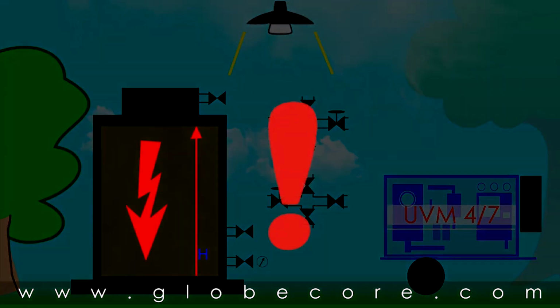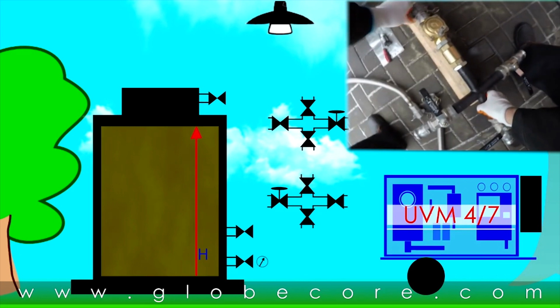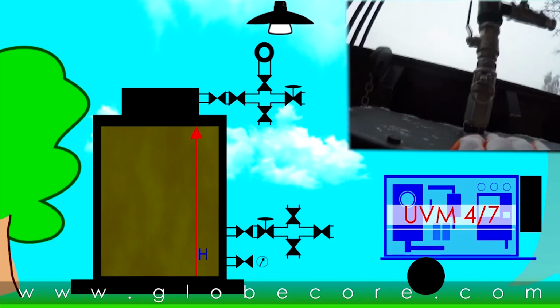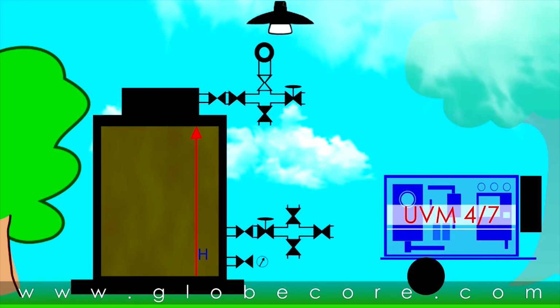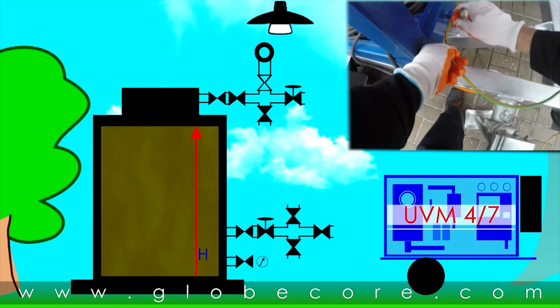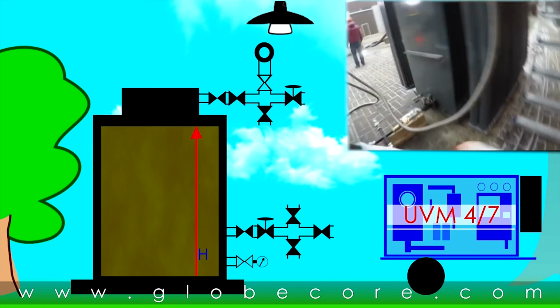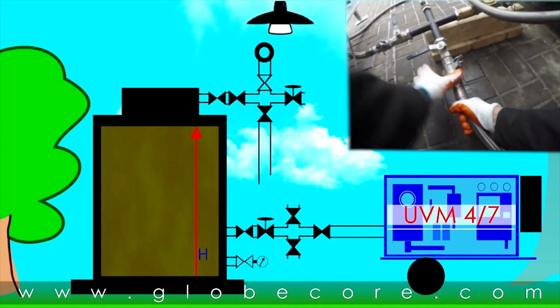Let's begin. Attention! For preparation and connection of the TSS system and the pipelines, the transformer must be offline, and the valves of the transformer must be closed. The upper and lower crosspieces of the TSS system are connected to the transformer. The TSS pressure sensor is connected to an available port of the transformer. The required oil pipelines are connected to the transformer.